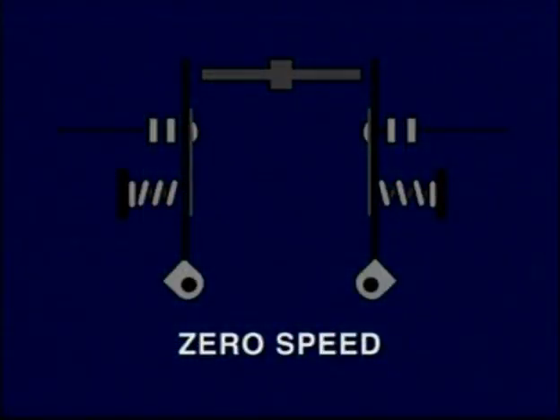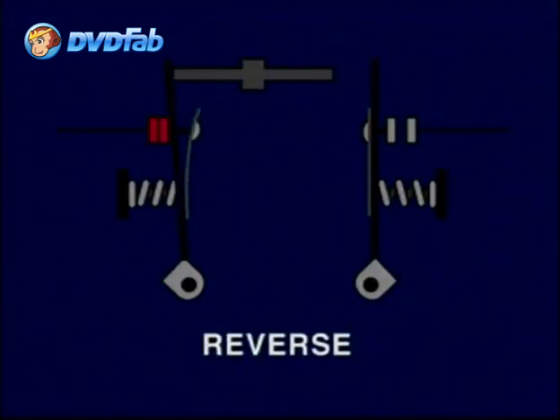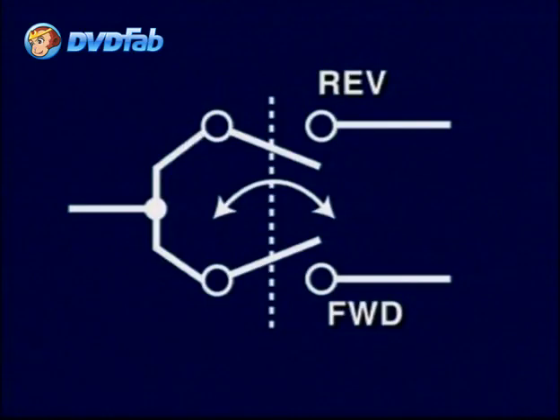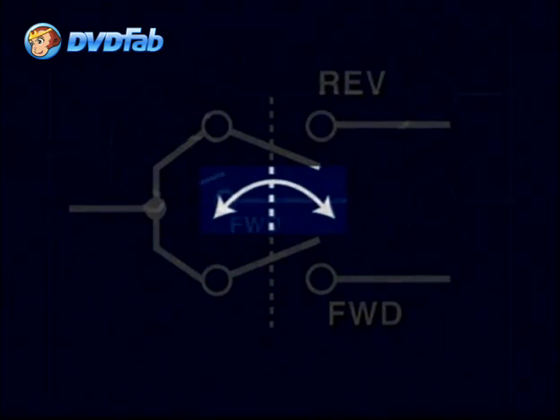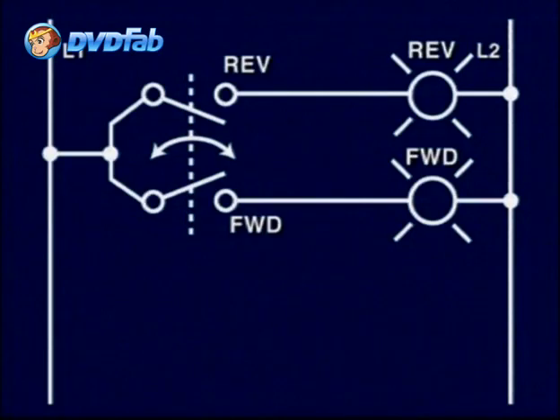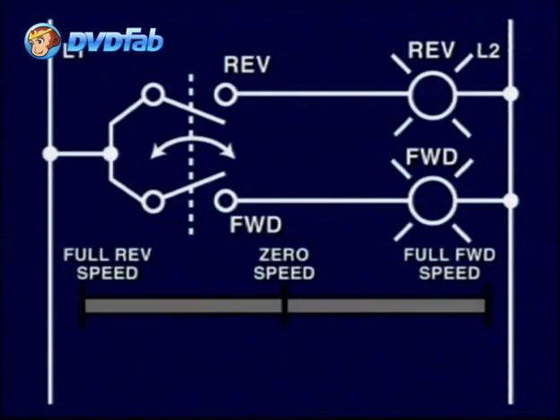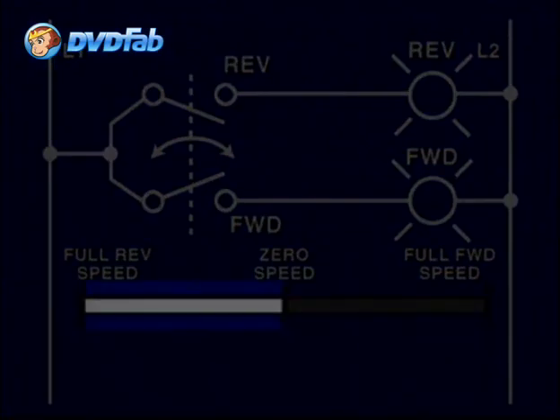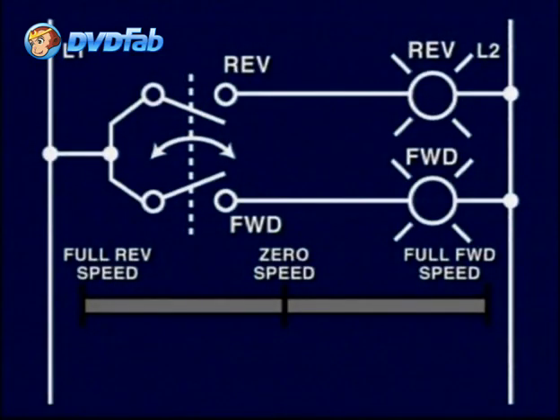Inside the switch, there are two sets of double-pole, double-throw contacts, which open and close according to the direction of the shaft rotation. The mechanism that actuates these contacts is a centrifugal switch, which we'll see in operation in a second. The plugging zero-speed switch is represented by this symbol, where the circular arrow indicates a rotating type activation switch. We can graphically represent the speed of a motor like this, where the motor can go to full forward or reverse speed according to a motor control circuit.